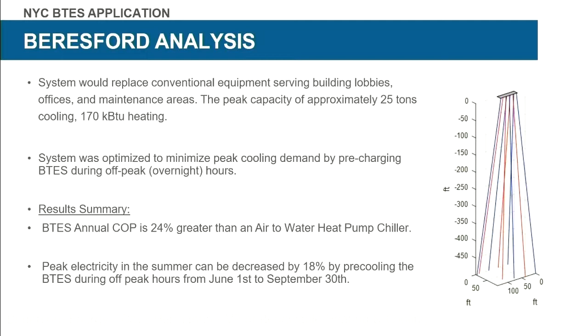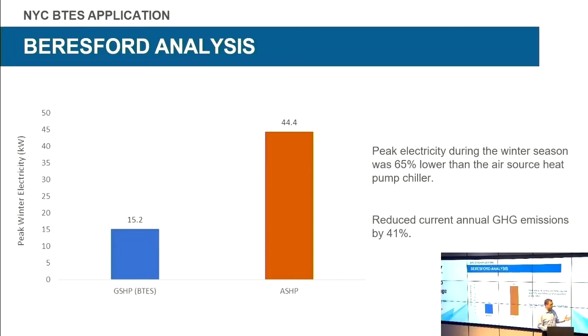It also provides all the benefits of ground source for coefficient of performance, very high COPs during heating. What I like to illustrate is that during heating, this system is about 64% more efficient than an air source solution. So it's quite dramatic. The COP for a system like this hovers around 4 during the coldest days of the year. And that's it.